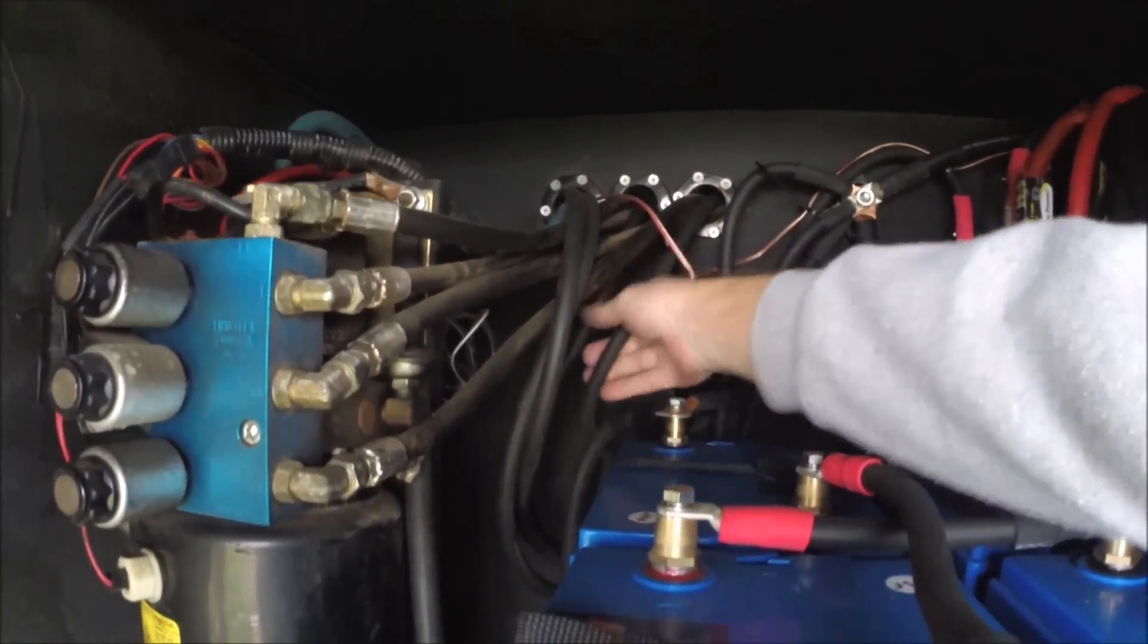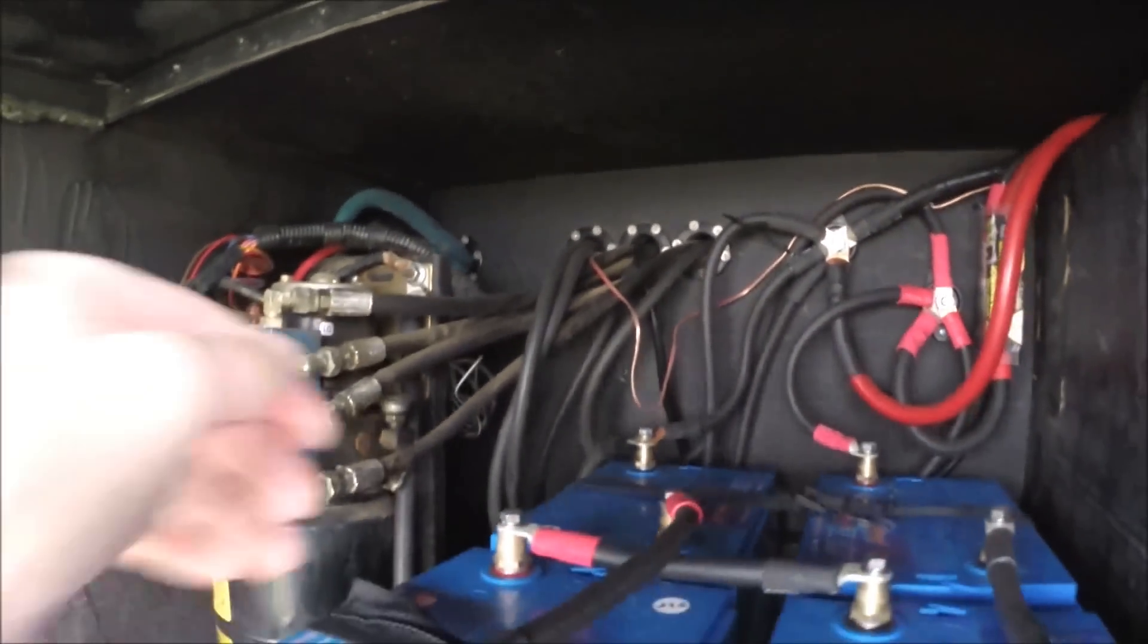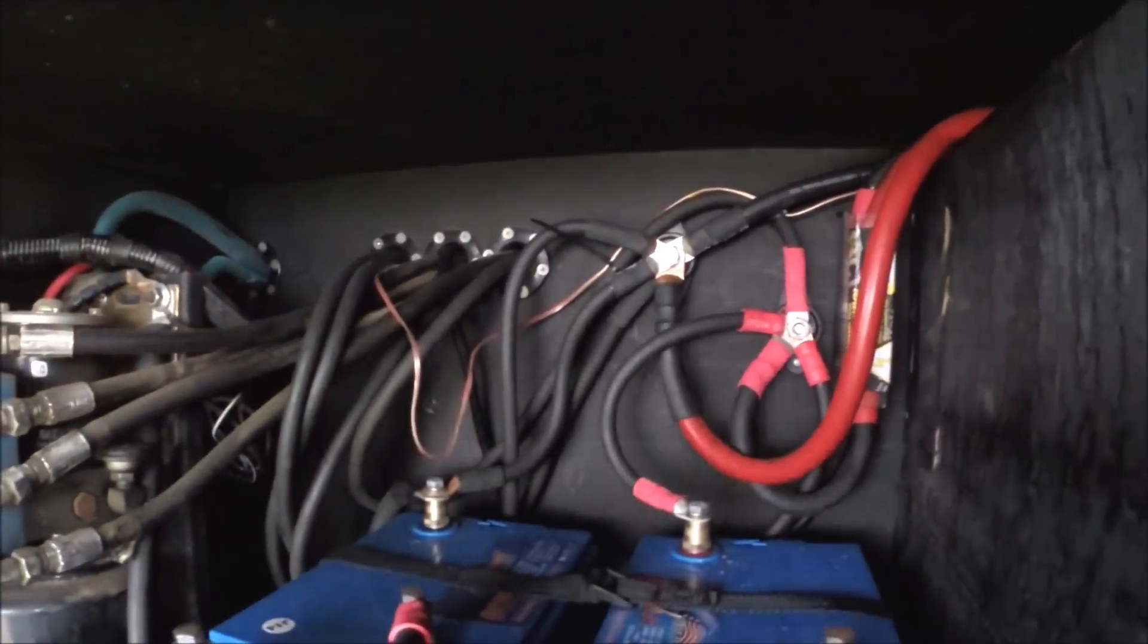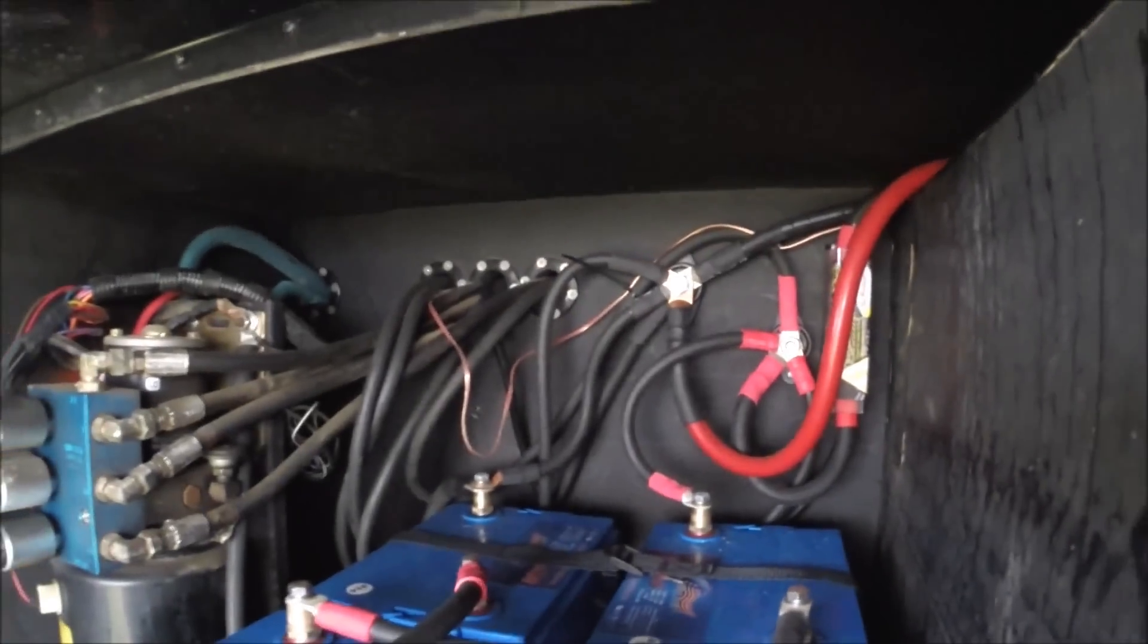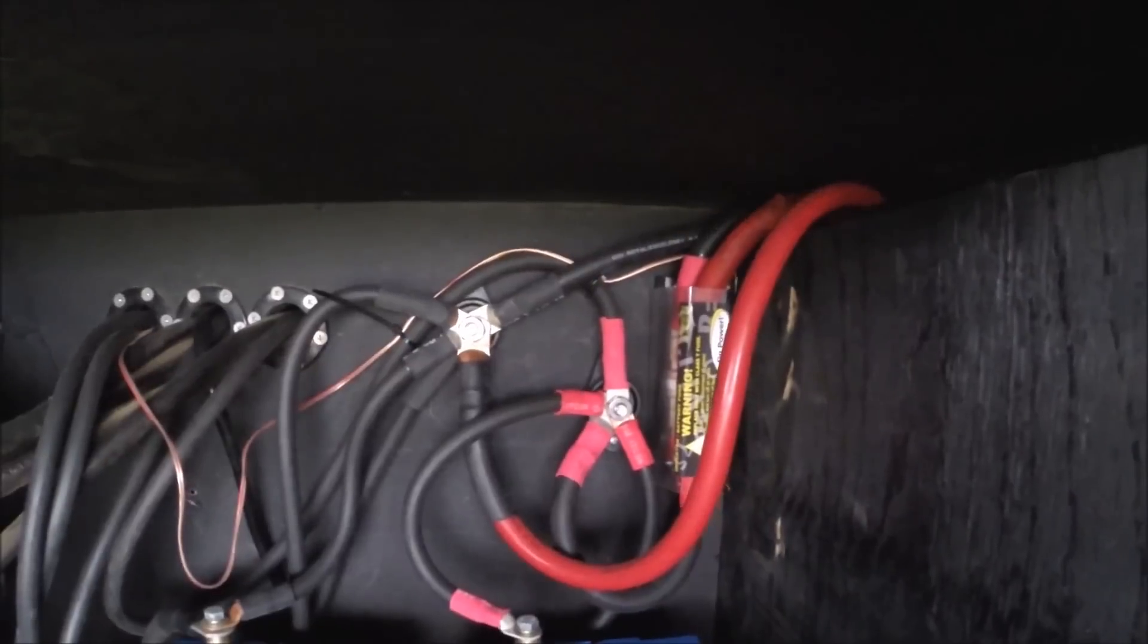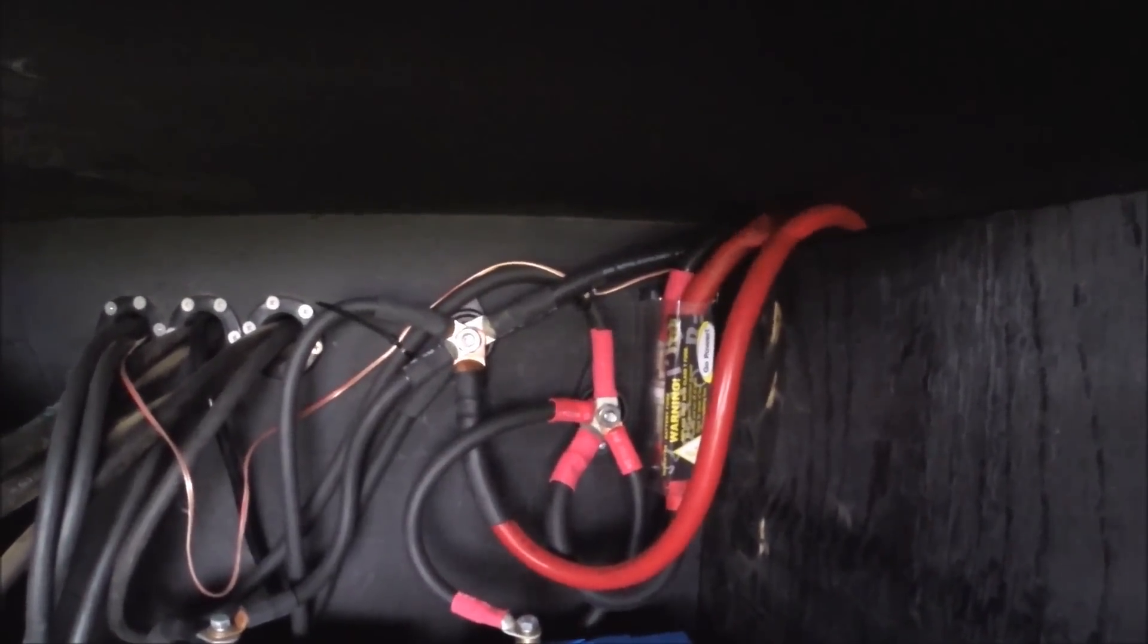There's two of them right here and two of them right here. These two one-ought, that's what he's brought. And then there's these two. And he's putting a couple of those terminals up in here. This is what he was saying is considered the middle. And there's this that goes over to the inverter. You know, he's feeding it from the center. That's the one fuse we got, and that fuse there, what is that fuse? It's a 400 amp and it's going between the full output of this thing. And that's going to the inverter here, that goes to the inverter. So he has one fuse in the fuse going to the inverter, that's a big 400 amp.